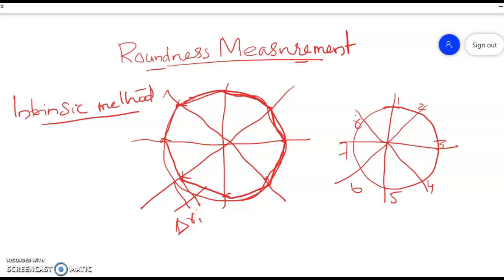In the extrinsic method the question is: which circle do we use as the datum? Consider the rotating table type of roundness tester. The workpiece is fixed over the rotating table, which rotates about its own axis. It is very difficult — practically impossible in precision work — to align the center of the workpiece exactly with the center of the table, so we are left with some eccentricity.